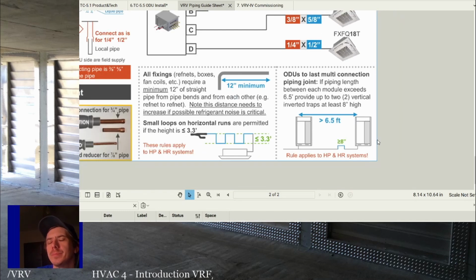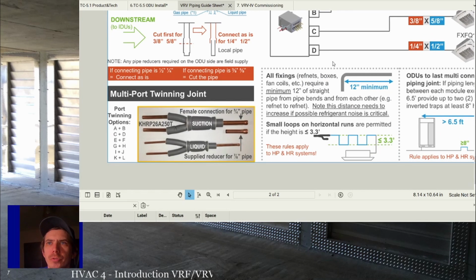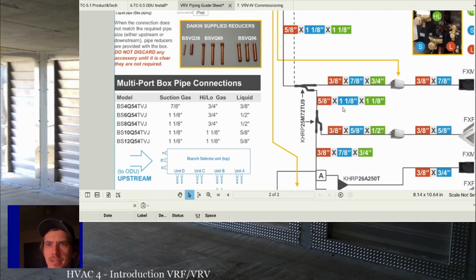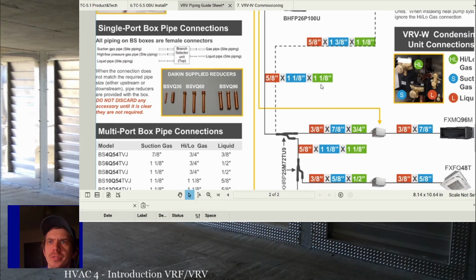And then they have rules in between outdoor units that you'll need to keep in mind. We're not going to go through that in detail. I don't know if these rules are as common between manufacturers. In general, you're not going to have situations where outdoor units are more than 6.5 feet apart anyway, so it's not that big of a deal as far as outdoor unit connections. Doesn't mean you don't need to follow the rules, but I don't think it's as universal across manufacturers. Again, they supply you reducers and these branch selectors and stuff like that.